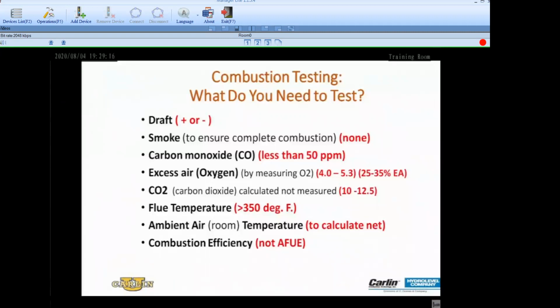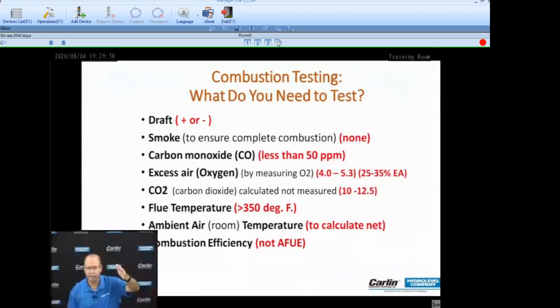So understand smoke. Carbon monoxide: we try to get levels less than 50 parts per million, less than 100 parts per million. The code numbers are actually quite a bit higher than that, and they're acceptable. But for good combustion, there's no reason we shouldn't see low ppm. How much excess air? If you wanted perfect stoichiometric combustion, 15.5% CO2, then you're going to have no excess air. But with the imperfect equipment that we have, there's always going to be excess air. And here's that oxygen level again, 4.0 to 5.3.